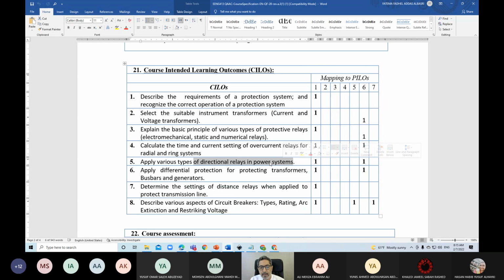Then following the differential protection. This is another principle of detecting fault by comparing the currents entering and leaving components. So we call it differential. We take the difference between those currents and decide whether there is a fault inside this component or this equipment or not. And we will apply this principle to transformer protections, busbar protection, generator winding protections, or motor winding protections also.